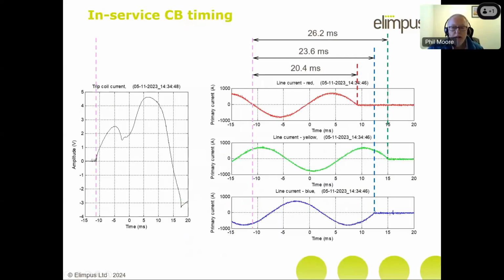In common with all circuit breaker monitoring systems, we can time the circuit breaker. So this is the trip coil current, which we measure with a current clamp. If you're thinking that's a rather strange looking signal, it's because we tend to use AC clamps because they don't require batteries and they're a lot easier if you're leaving something on site for a few weeks or so. And in reality, it's only the beginning of this signal that we're particularly interested in.